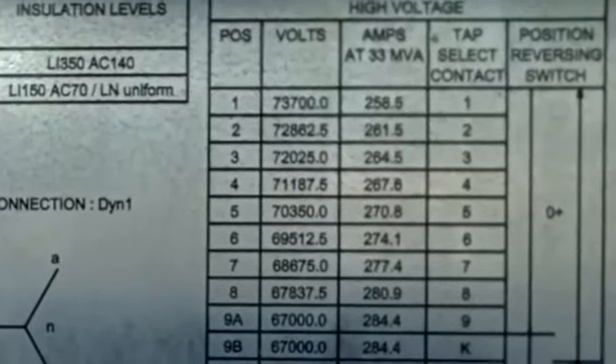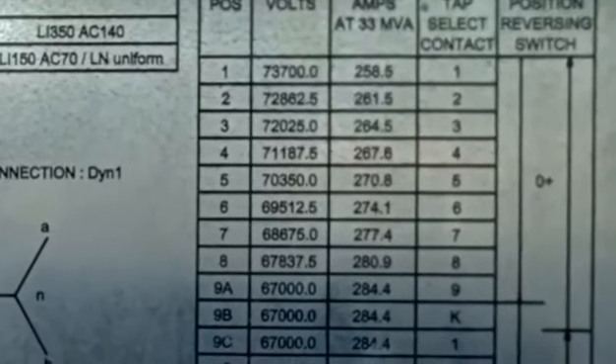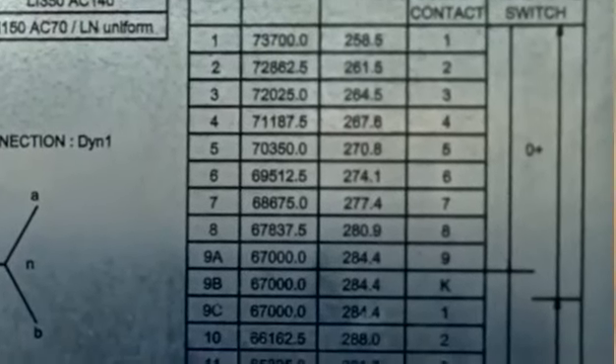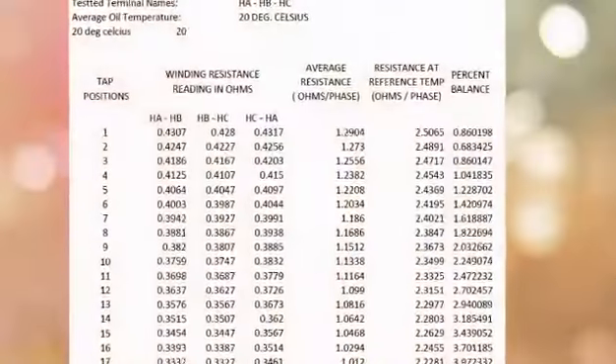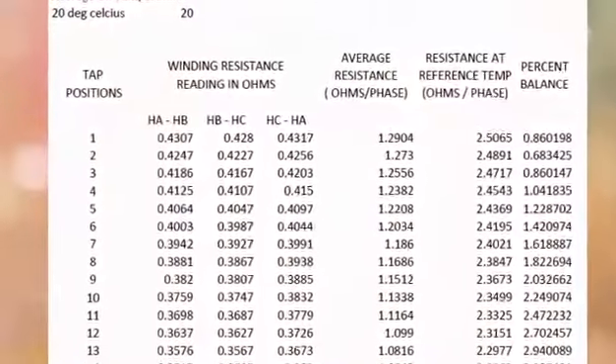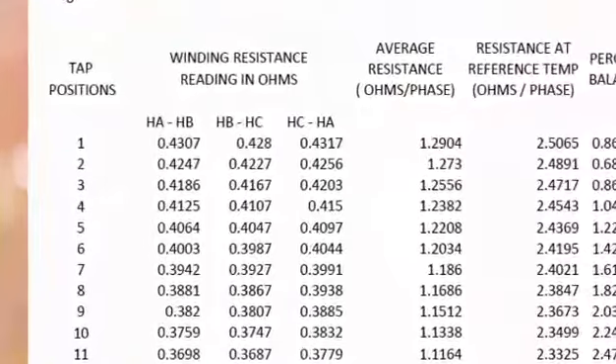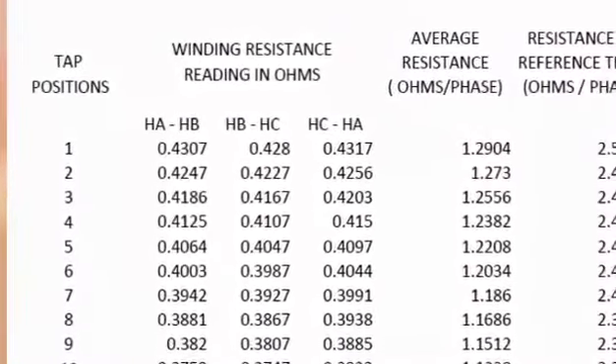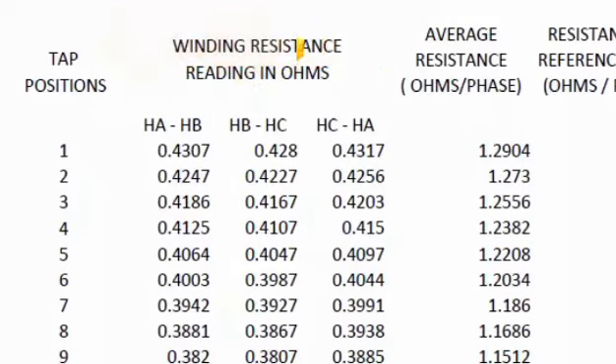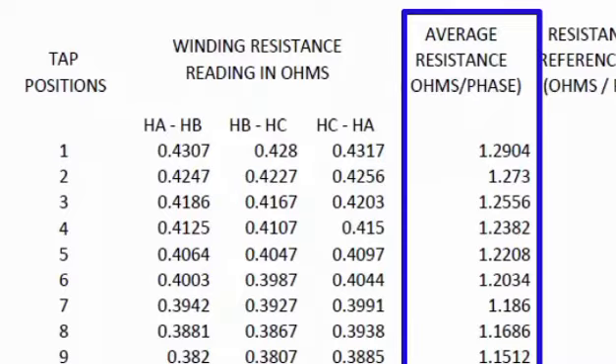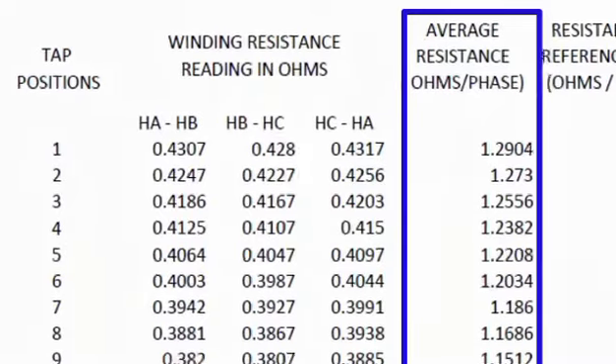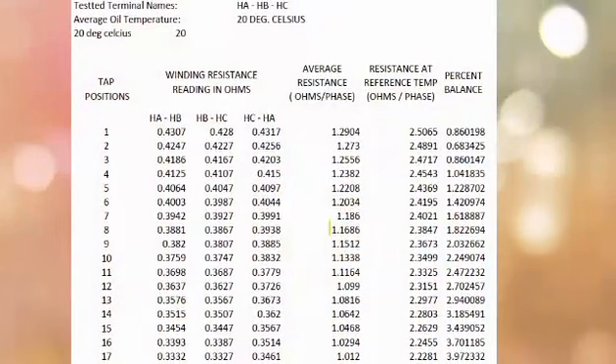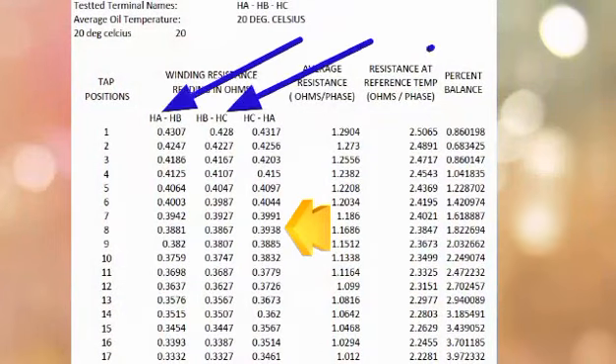Readings are established as the instrument starts testing, until stabilization of the current. HV side resistance R1, LV side resistance R2. Then record the measured values for each phase and tap. But depending upon the test instrument, it will automatically show the measured values and export them to a specific file type, including the mean or average value and the converted standard winding resistance. These mean resistance values came from the 3 winding resistances measured by the tester on the primary side in each phase: Phase A, Phase B and Phase C.